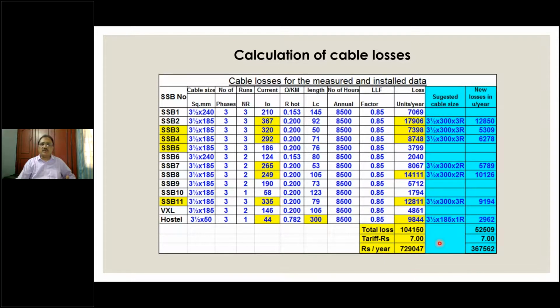Now, this could be useful for many industries which are putting up newly. For existing industry, when you make a suggestion, you have to include other parameters. What is the voltage drop? What is the power factor? What is the short circuit current? And the losses. So when you do an audit, if all the 4 parameters can be taken, clubbed together and the benefit is shown to the customer, I'm sure we will be able to persuade the customer to replace some of the cables. The average cable life is about 20 to 25 years, but sometimes based on the payback, it is possible for us to educate and persuade the customer to replace some of the undersized cables.